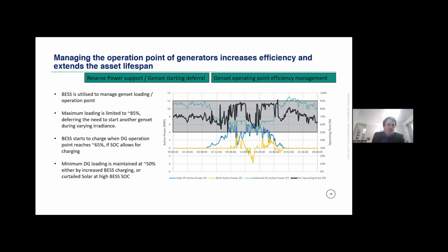Further than that, what we also applied was charge management from our renewable generation. What we ended up applying was to allow the solar PV to charge the battery once our generator reaches a point of 65% operation, which is still in its high efficiency range. So once our solar PV injection reaches levels where the generator is sitting at 65%, we start charging the battery and keep that operation point at 65%. Only once full state of charge has been achieved by the battery do we then further reduce the operation point down to 50% of the genset.